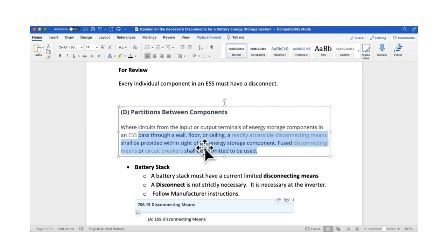And then also another thing is, say you're using that combination, the LG Chem and the SMA, it is listed as a system already. So SMA and LG Chem got together and they listed it as an energy storage system. And so that energy storage system listing is probably going to meet all of your requirements. And so I would like to think that that button on the LG Chem battery is a disconnecting means. Okay. Because you push that button on the LG Chem battery and it turns it off.